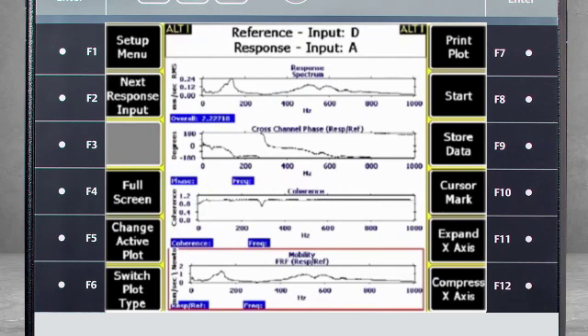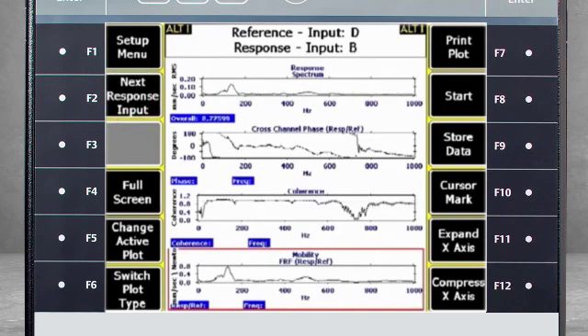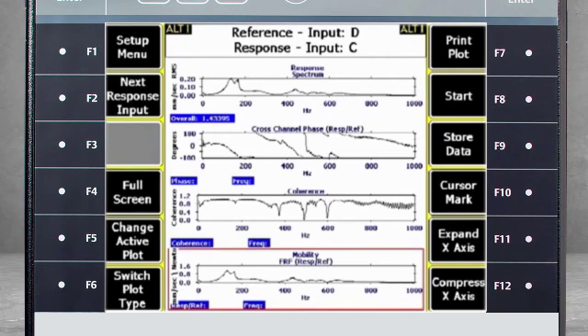Now you see the four plots you selected for viewing. You can see that there is a natural frequency in direction A of my sensor. Use F2 Next Response Input to toggle between A, B and C response input versus D reference input.